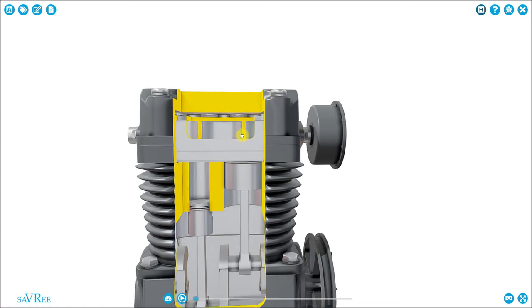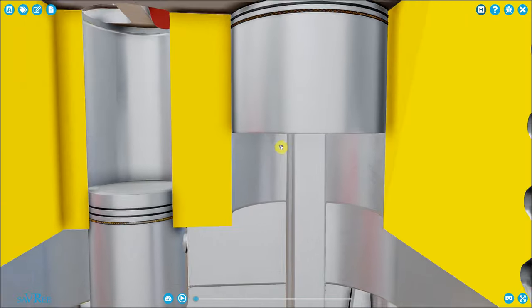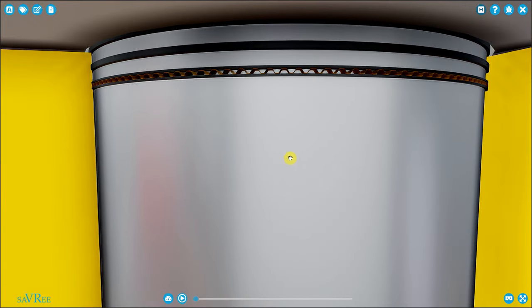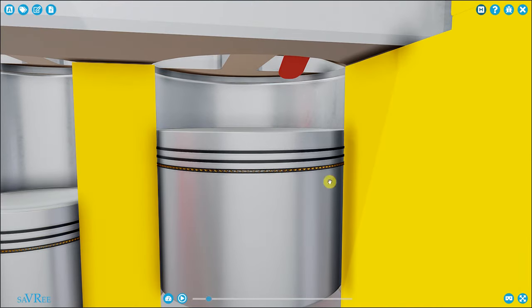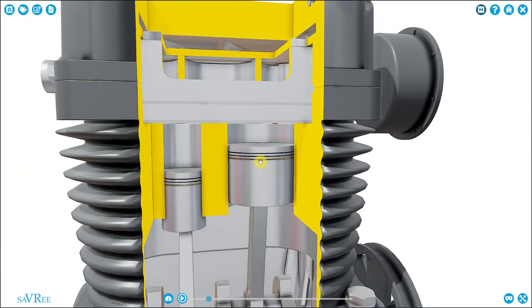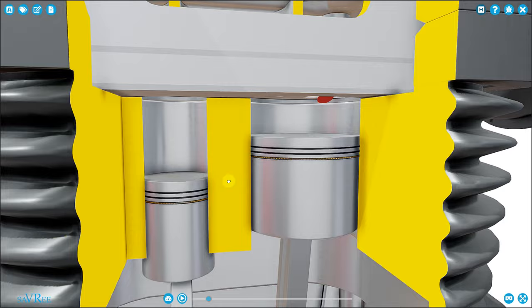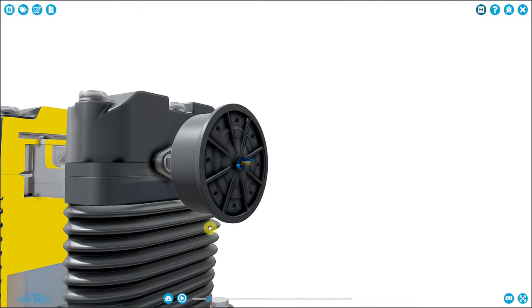We filter the air going into the air compressor because we don't want to damage our internal air compressor parts. The clearances between the piston and the cylinder, which is the item the piston moves up and down within, are very small. Piston rings seal the space between the piston and the cylinder, as you can see in these highlighted areas. Any particles of dirt, grit, or sand drawn into the air compressor would damage these very fine clearances between the piston rings and the cylinder liner. So we have an air filter to filter out those bits of sand, grit, and dirt.